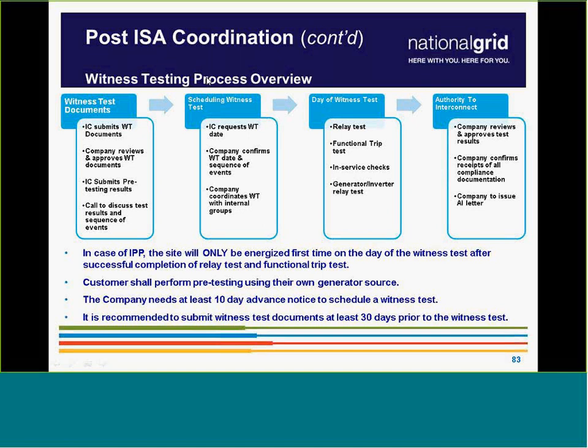The witness test is scheduled only when all documents are accepted and construction is complete on both sides. On our side that means all overhead construction is done, substation work is done, the recloser is hung, control boxes are installed, and office and field commissioning is complete. That's the only time we can schedule the witness test and proceed with testing.